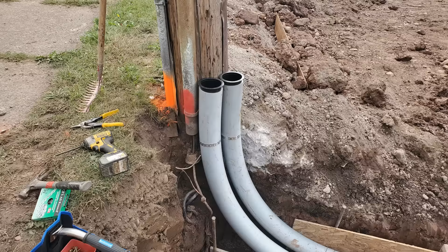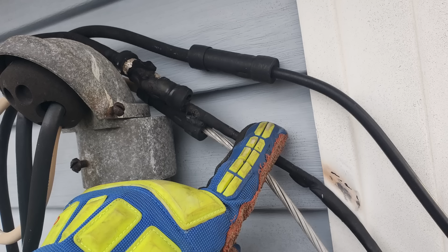This photo is from November 24th, 2021. You can see how the two hots and the neutral are wrapped right up and around the grounded weatherhead. You can actually see the bare spot that's only millimeters away from a dead short. It's melted quite badly, and that connection is pretty well ready to fall apart.